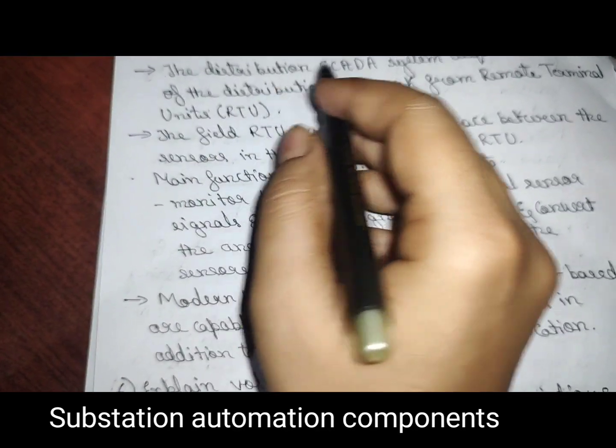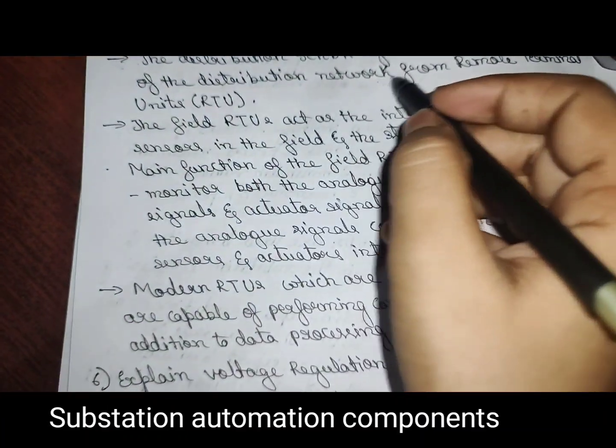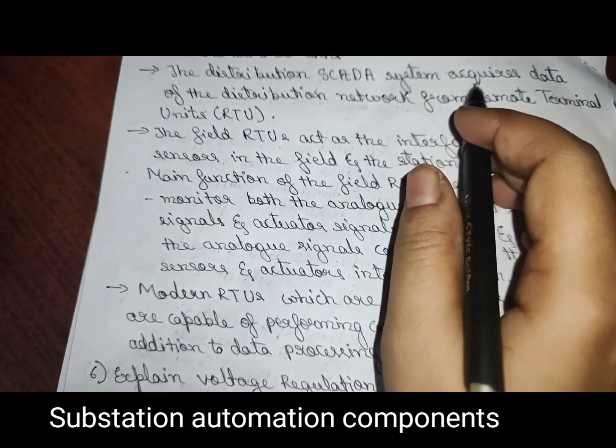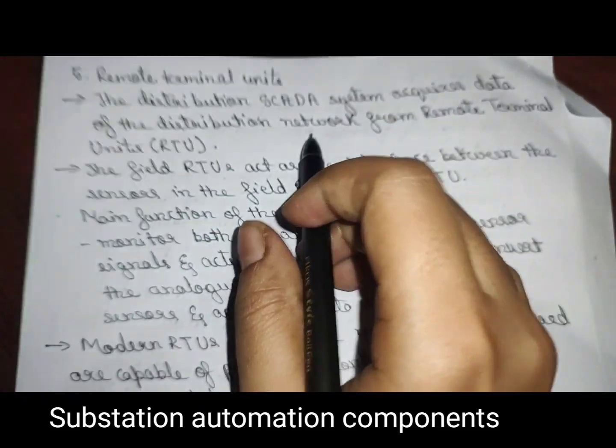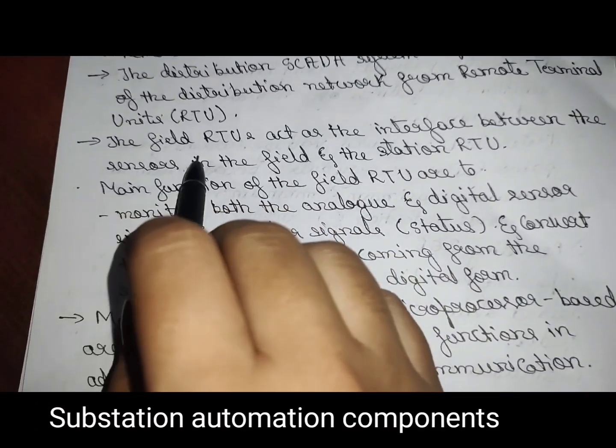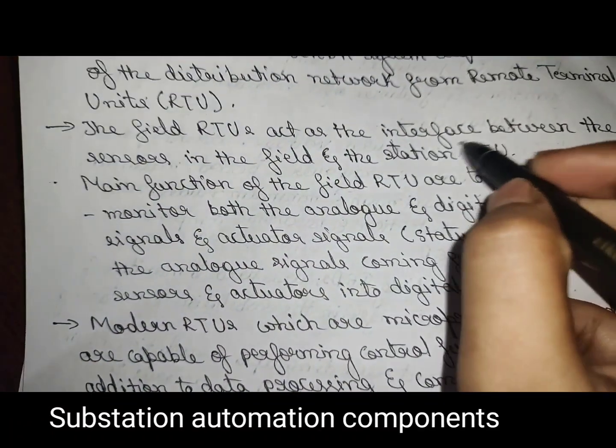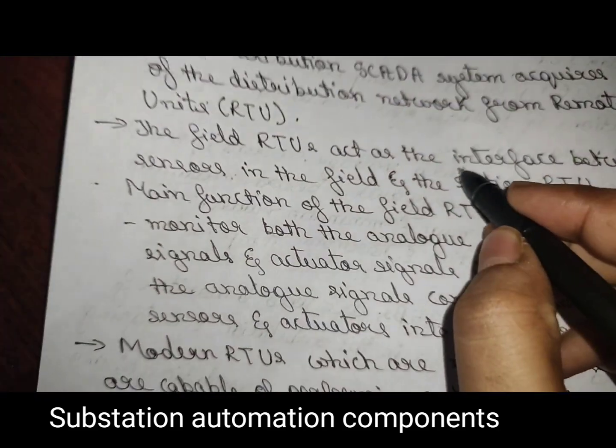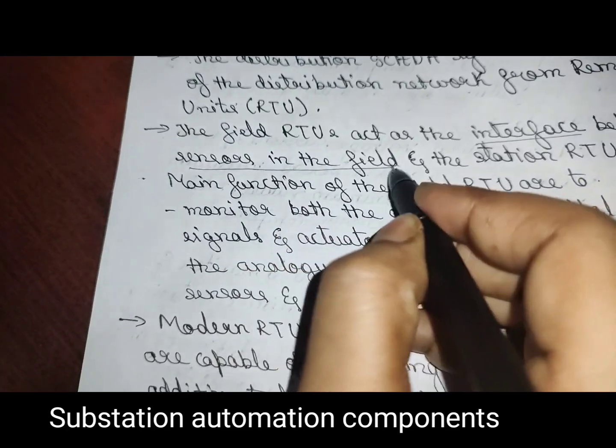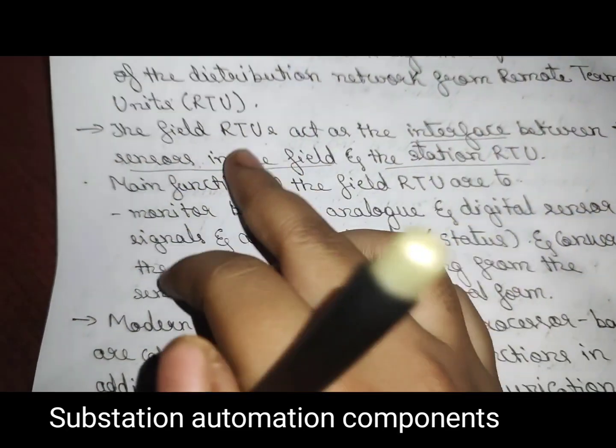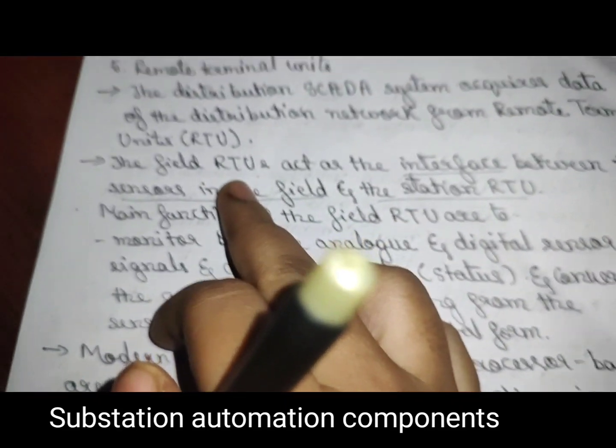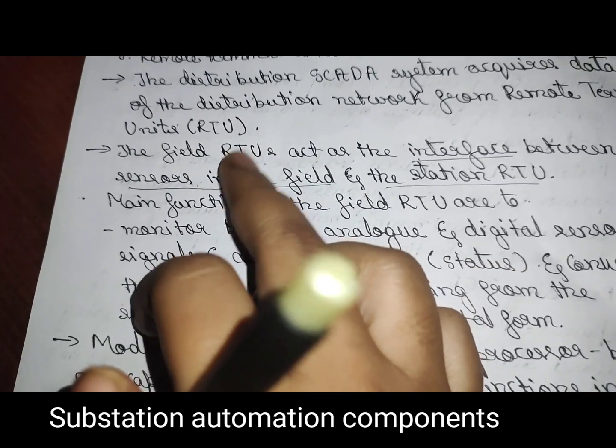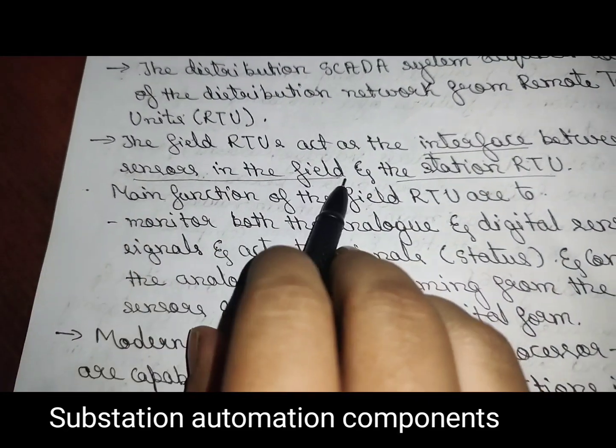The fifth one is the remote terminal unit. Here the distribution SCADA system acquires data of the distribution network from the remote terminal units. So SCADA acquires the data from the remote terminal units. The field RTU acts as the interface between sensors in the field and the station RTU. It should interface; only then can it collect the data of the equipment.